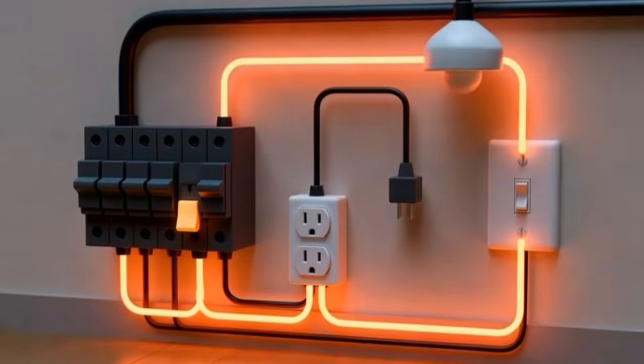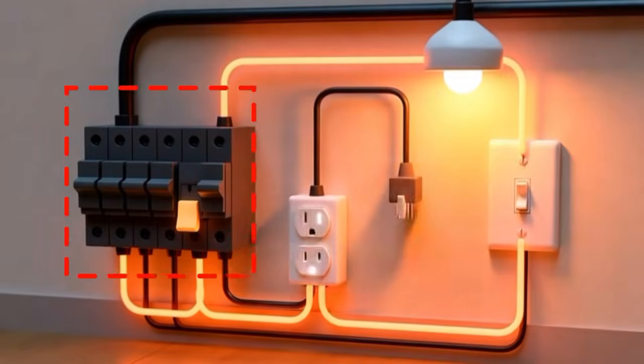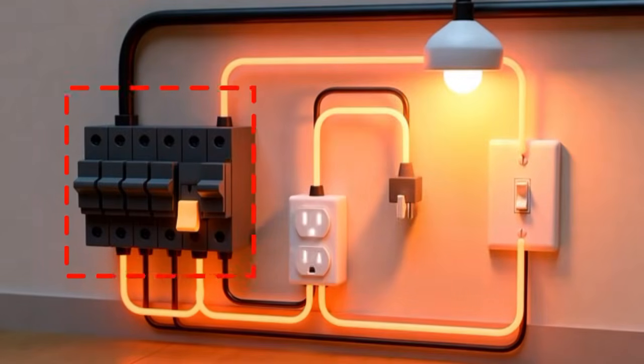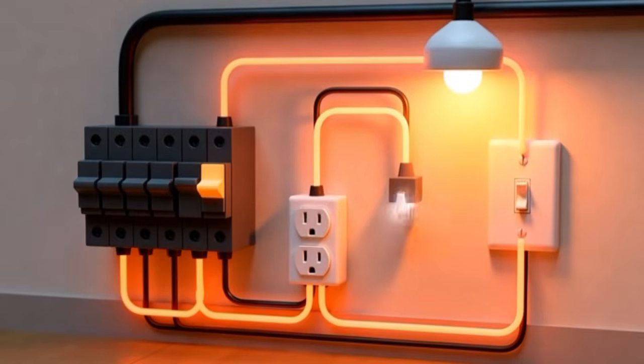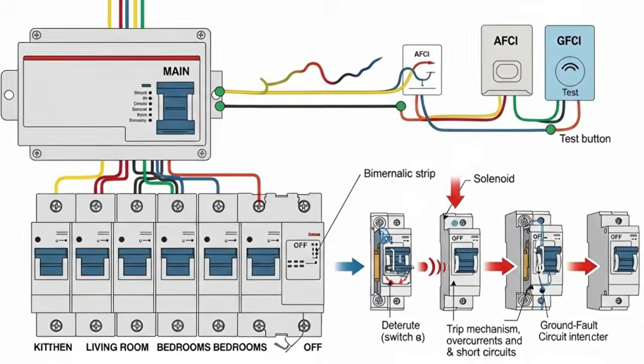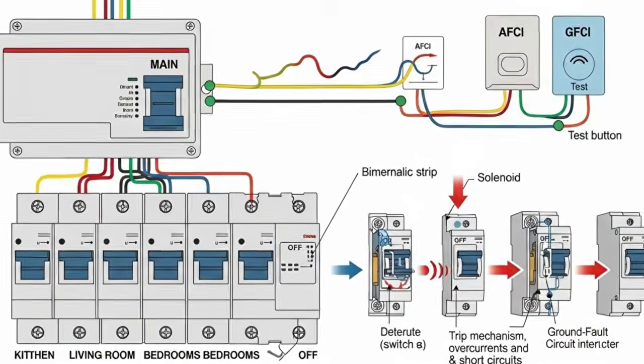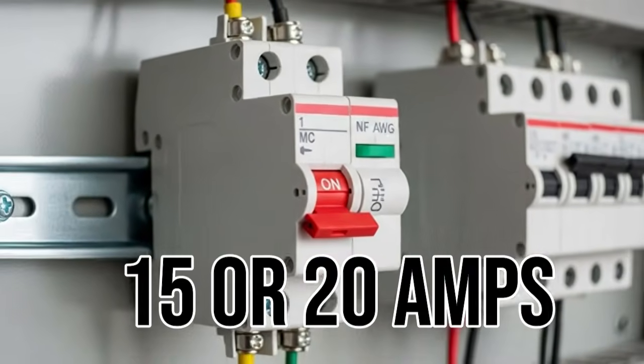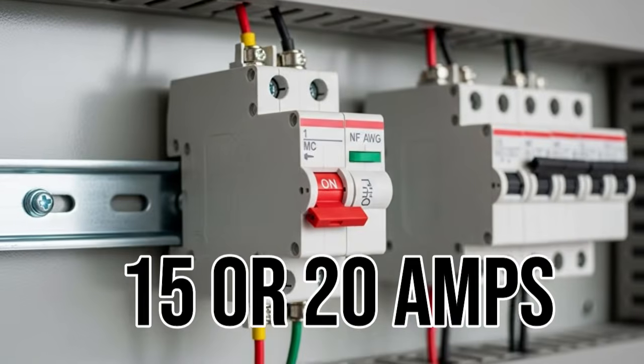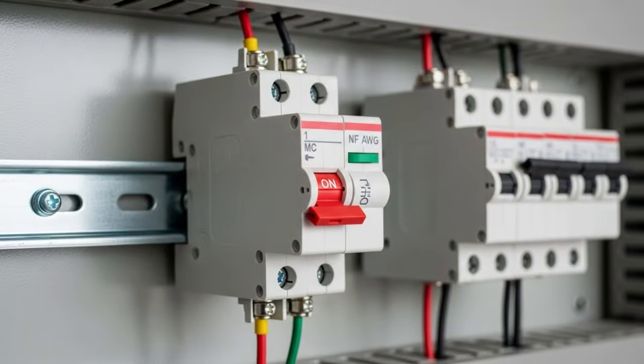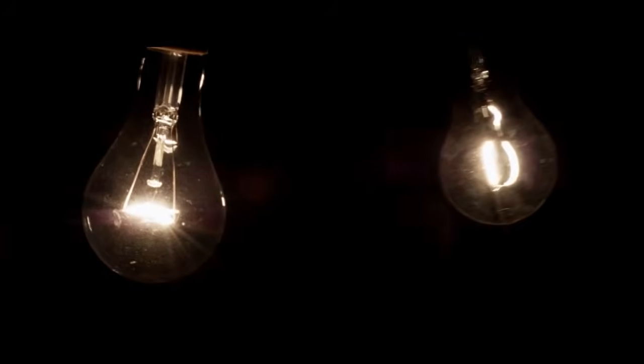To understand why a breaker won't reset, you first need to understand how breakers work in the first place. A circuit breaker is an automatic safety switch. It monitors the electrical current flowing through a specific circuit in your home. Every breaker has a current rating, usually 15 or 20 amps for standard household circuits. As long as current stays below that rating, the breaker remains closed and electricity flows normally. But when current exceeds the safe limit, the breaker trips.